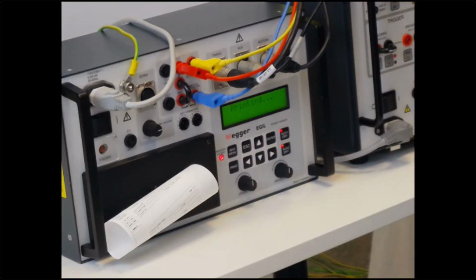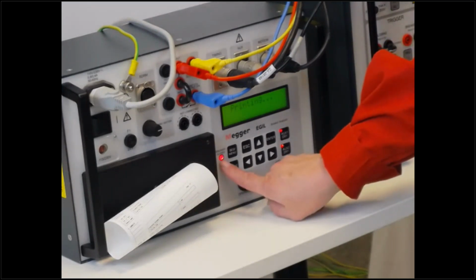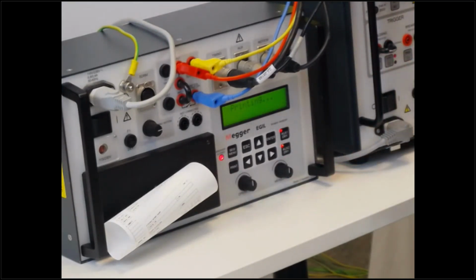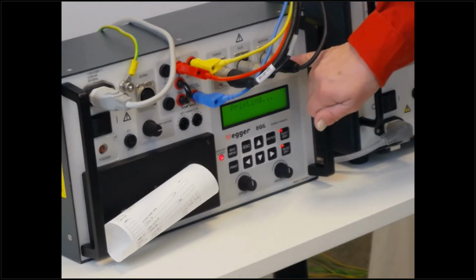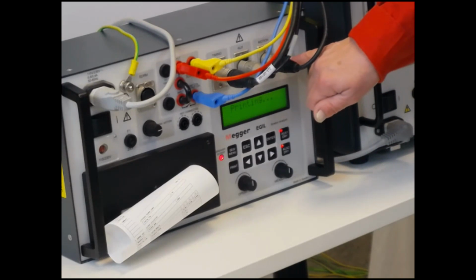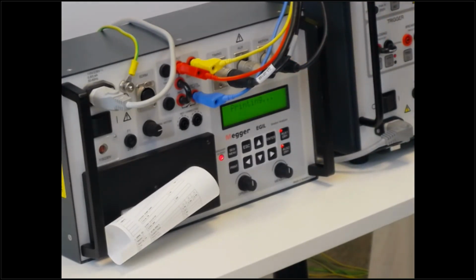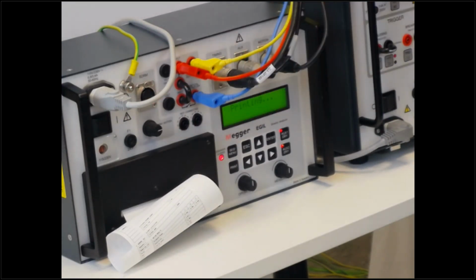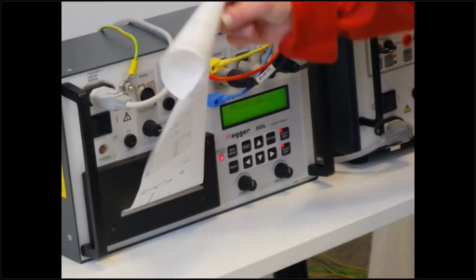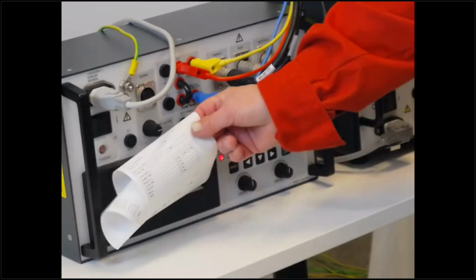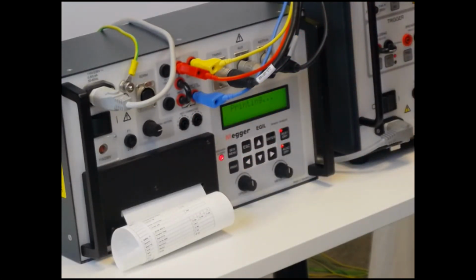While we're waiting, we can check. Yes, the breaker is closed. Another thing we can check is, I said we have communication possibilities. If you want to communicate, you're going to use a USB on this instrument. And the instrument also has the possibility to do this advanced measurement Marius was talking about last hour, the dynamic resistance measurement, when you use this outlet. So we're going to get the same results, of course, as in the display. But here we're also going to be able to see the graph for coil current and motion.